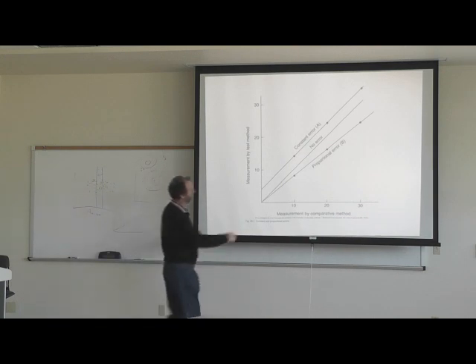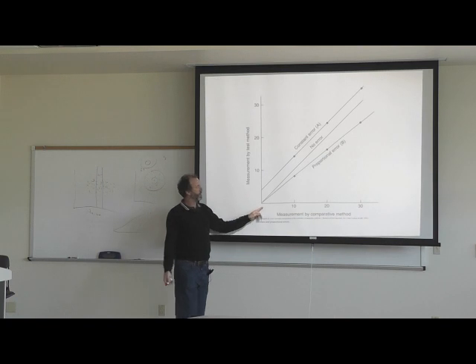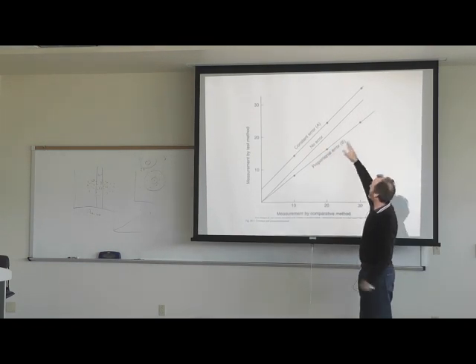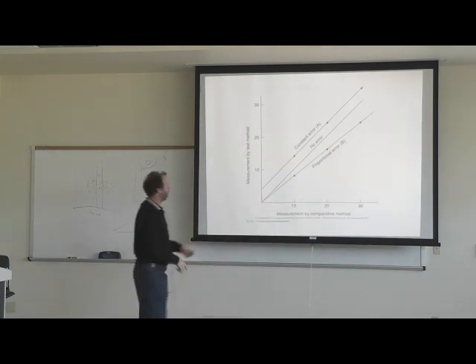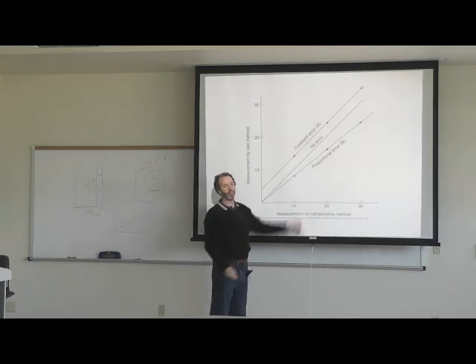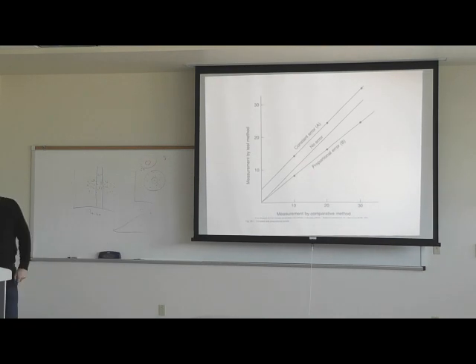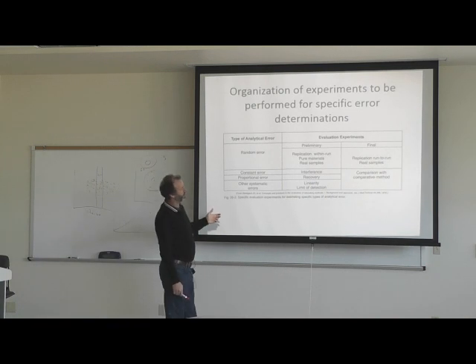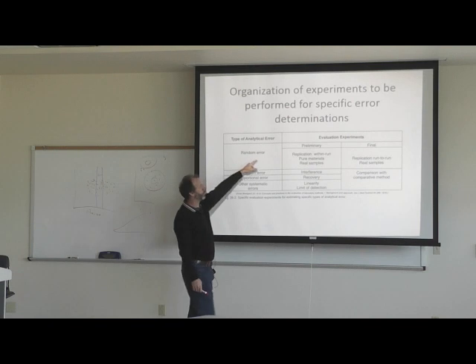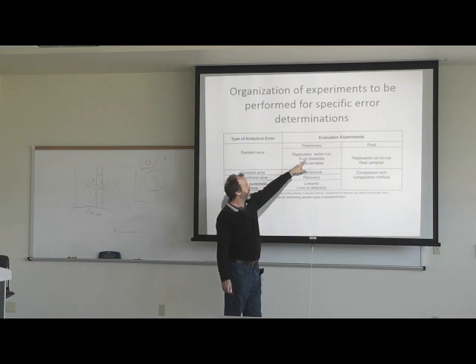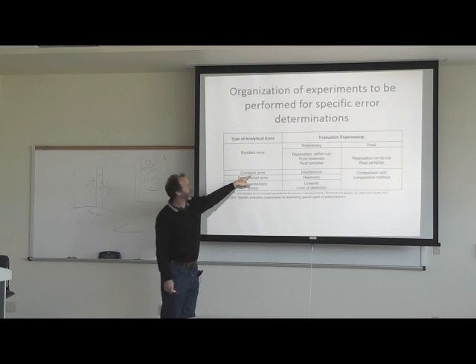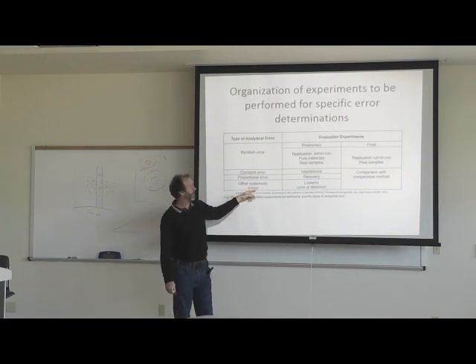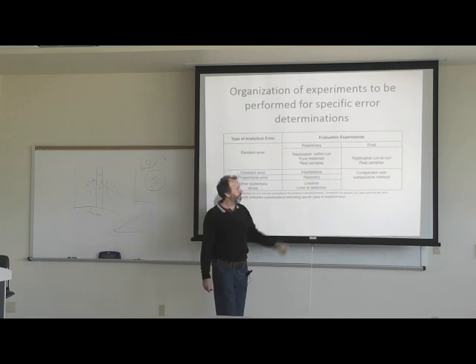Proportional error: when your measurement is low you don't have much systematic error, but as you increase the measurement the systematic error increases too. Constant error never changes — it's always off by that certain amount. To measure these errors experimentally: for random error, do replication within-run experiments using pure materials then real samples. For constant error, do interferent studies. For proportional error, do recovery studies. For other systematic errors, check linearity and limits of detection.